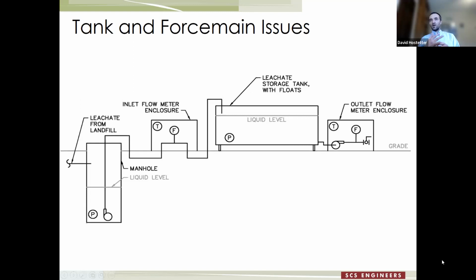And the cool thing about it is it actually catches two potential problems in one. First one is around the heater tripping out like we were talking about. And then the second thing that's happened every once in a while is that somebody will be out at the site inspecting something, and maybe they forget to close the door to that flow meter enclosure. So in either case, your temperature is going to drop, and we set an alarm on that thermocouple that says if the temperature drops below, say, 45 degrees, then an alarm goes out and the technician's dispatched to the site to figure out what's going on, whether it's a heater issue or whether somebody left the door open or maybe something else happened at the facility.